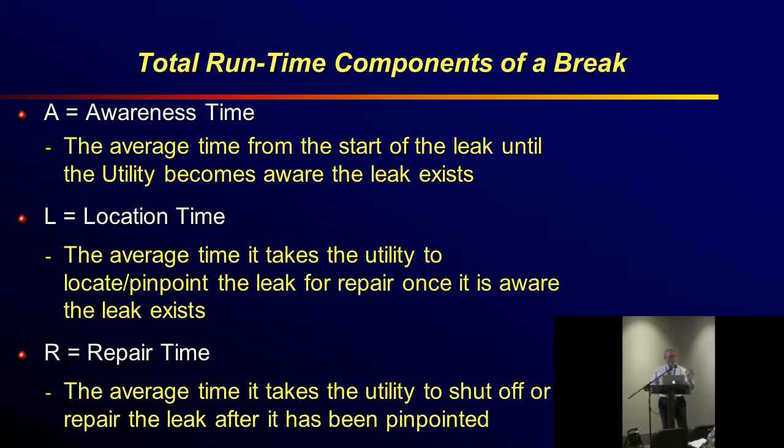This is where the DMAs will come in, the awareness flag. And what's your response time to go out to locate and find and pinpoint that leak? Should it be 1 day, 2 days, 3 days, 2 weeks, 2 months? If you start thinking about that, it will help you actually start designing how big your DMA is based on your system and your type of pipe. The two start to come together in terms of planned leakage runtime, DMA design, and the types of leaks that you have in your system. It all fits together. And you can start managing and planning time of reducing leakage runtime by putting those components together.